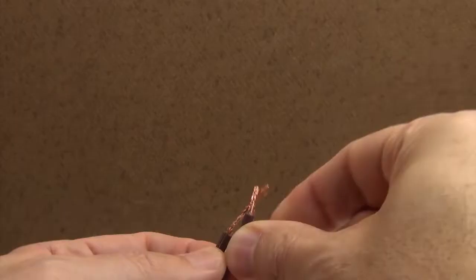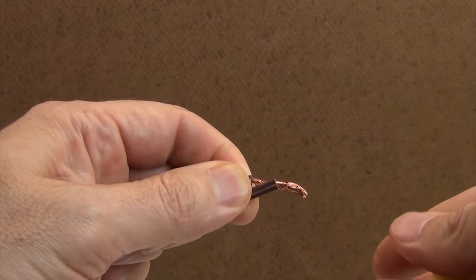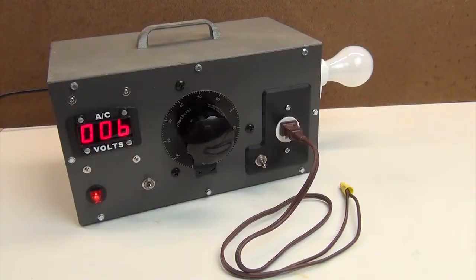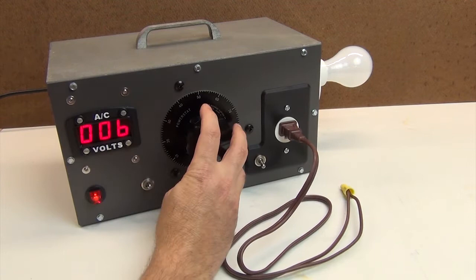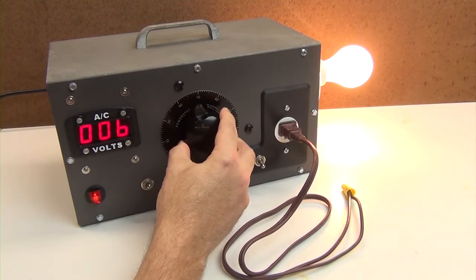I'll demonstrate what a fault looks like by deliberately making a short circuit in an old lamp cord. You can see that as I apply increasing voltage the light bulb comes on and glows brightly. That's the indicator that something is amiss and you need to stop the test.